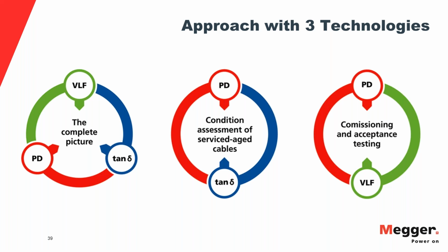Yeah. So I don't remember the question specifically, but it was along the lines of asking about insulation resistance testing, since that uses DC voltage to do the test. How do we square that with saying don't do DC testing? So the question is, I was told to always do insulation resistance testing first. This being a DC voltage, should this not be done? So that's the actual question.